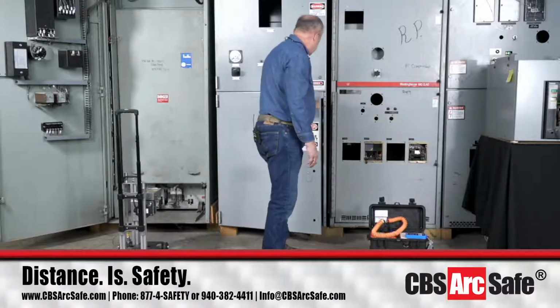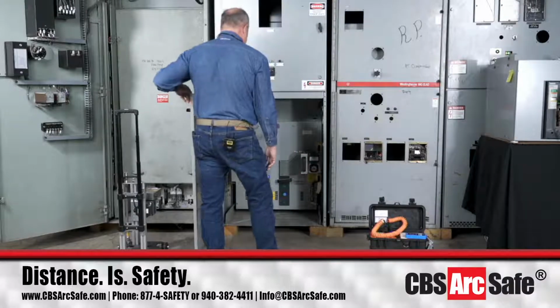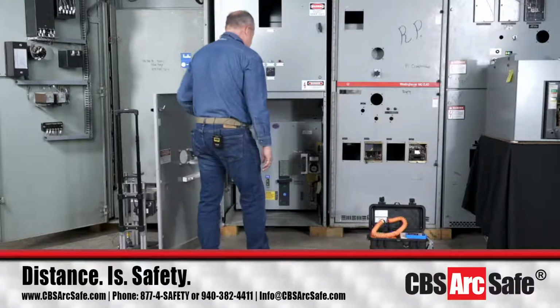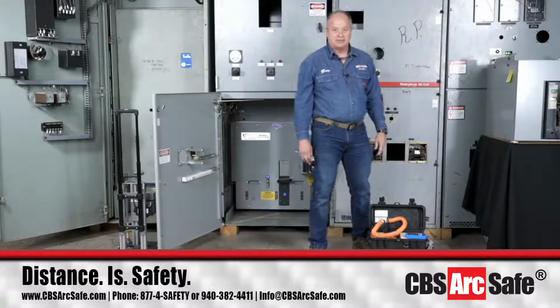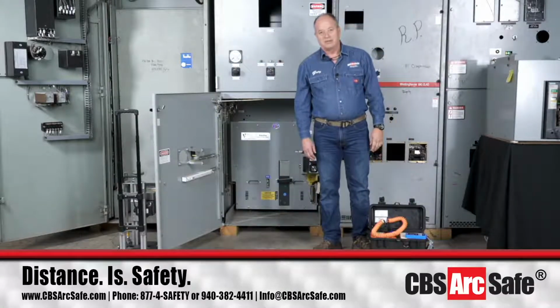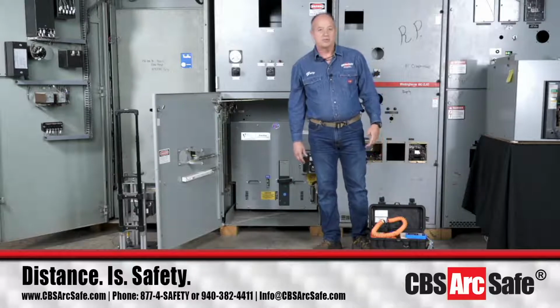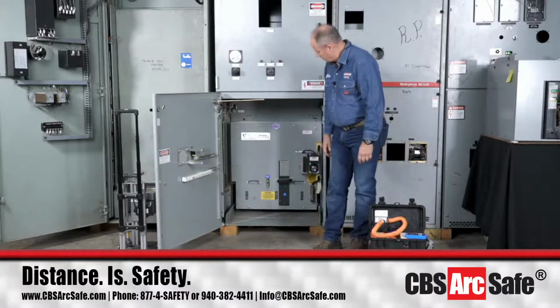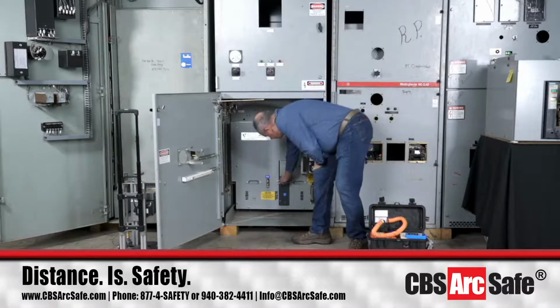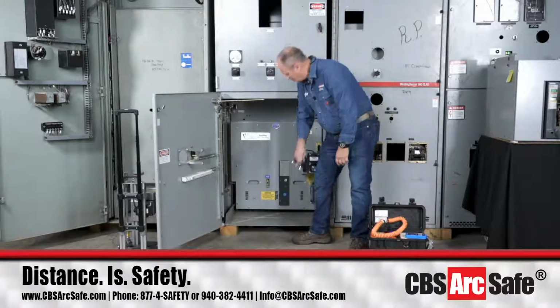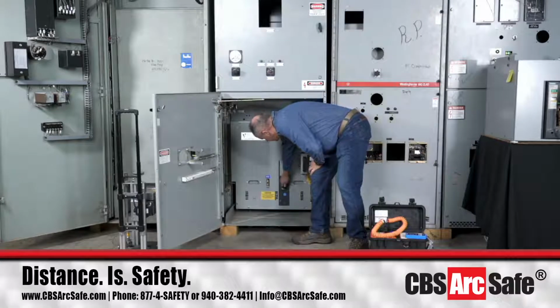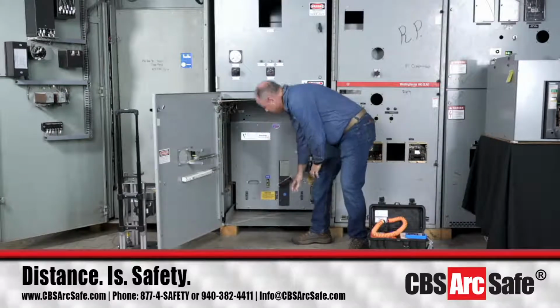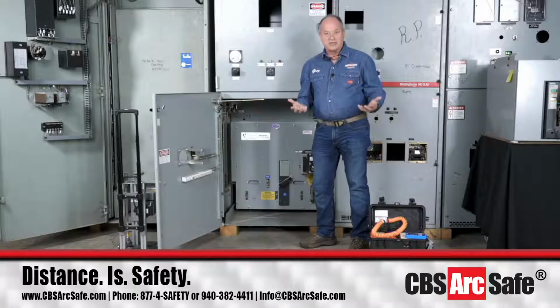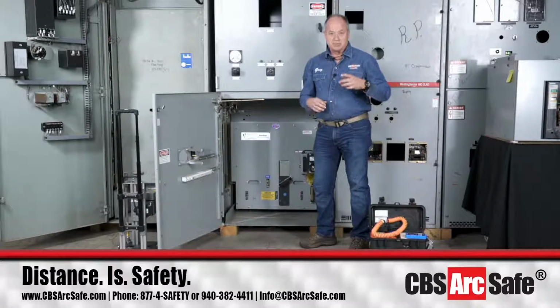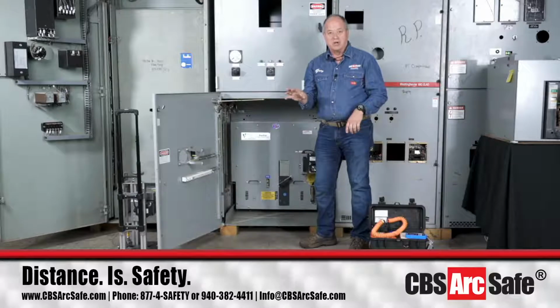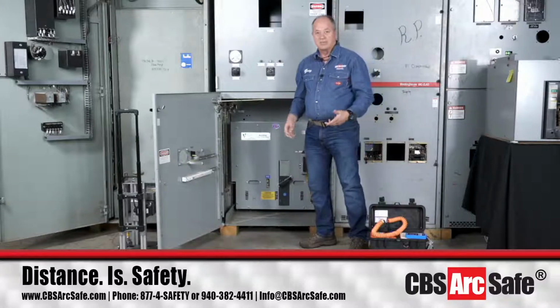The next one we're going to deal with is the PowlVac. Now the PowlVac is an interesting circuit breaker because it takes a three-handed monkey to be able to install anything on here to remotely rack or rack it out. So we use a trip defeat actuator on the trip button to automatically push that in, so now we're down to two free hands to get the racking mechanism exposed and put our RRS-3 onto the circuit breaker. That's what makes it so easy.